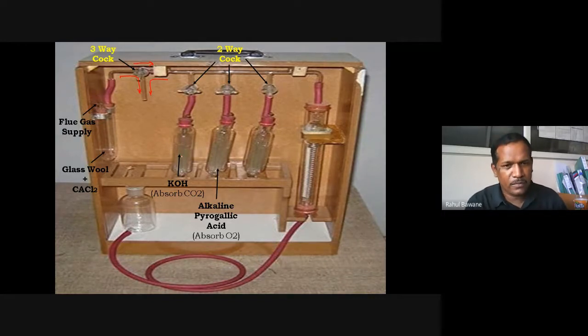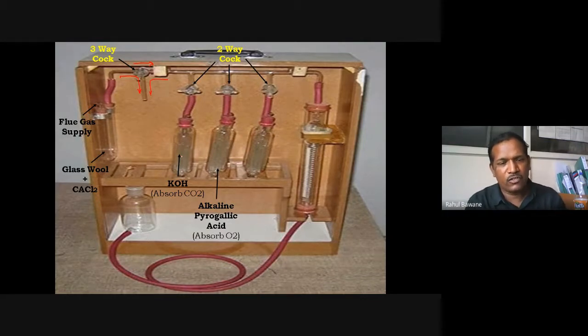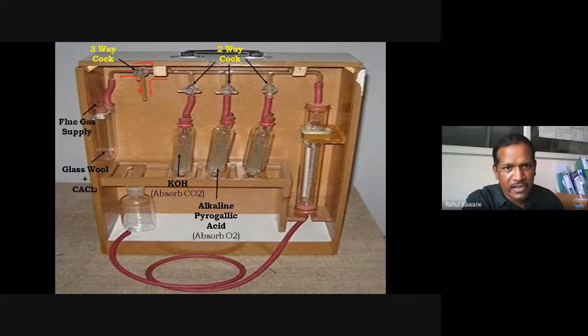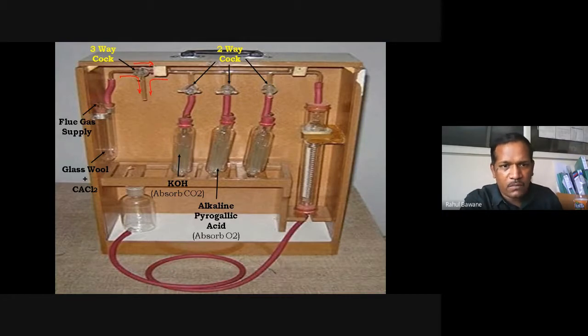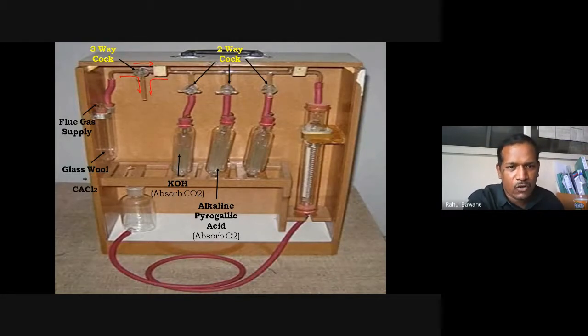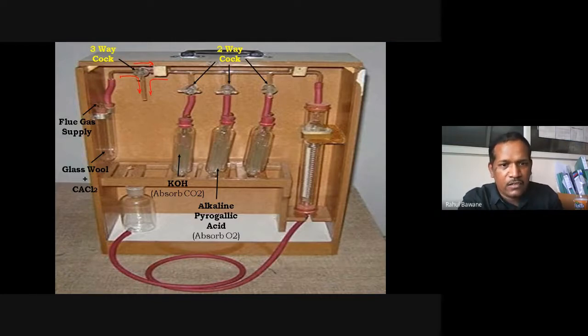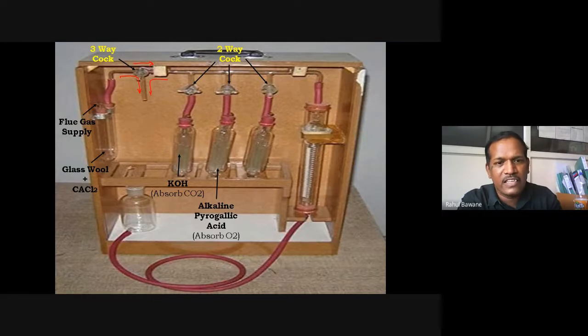The second bulb contains alkaline pyrogallic acid, which absorbs O₂. As asked in practical exams: it absorbs any O₂ — meaning not only free O₂ but also O₂ derived from CO₂. So if we directly send exhaust gas to the second bulb without first removing CO₂, the O₂ from CO₂ would also get absorbed, and we would not get a correct reading for CO₂ content.